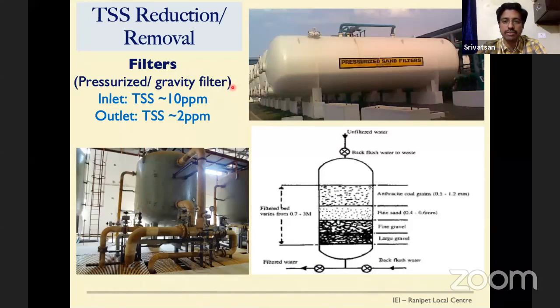The second stage of suspended solids removal is the filtration system. This one is called a horizontal filter. This is a vertical filter. All these filters have a similar bed arrangement internally, where water comes from the top and passes through various levels of media. One is anthracite coal, then fine sand, gravel, large gravel, and at the bottom, filtered water gets collected. This is like the natural filtration which happens in our ground. Here, the water from the clarifier with a TSS of 10 ppm goes in, and the outlet TSS level is around 2 ppm.